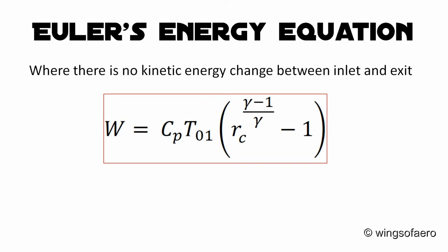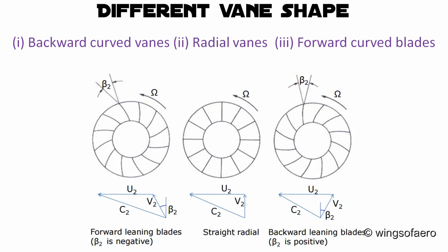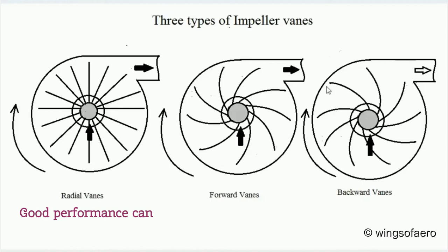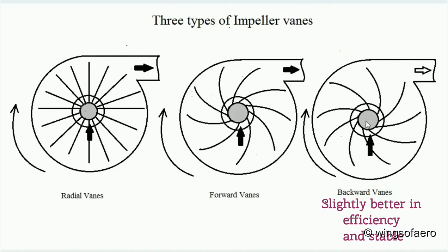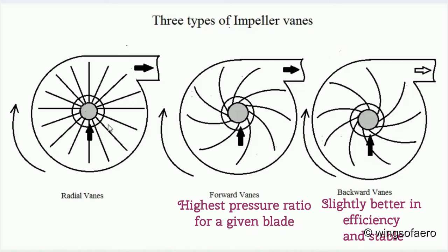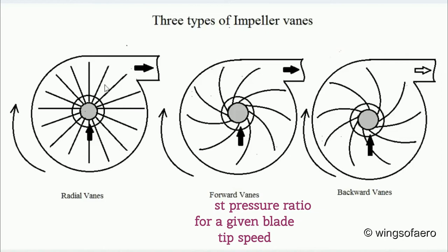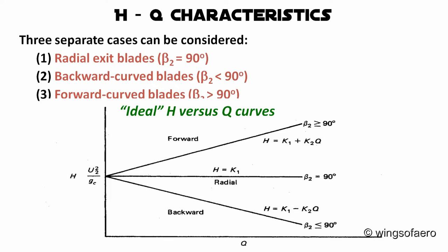Centrifugal effects on a curved blade create a bending moment and produce increasing stress, which reduces the maximum speed at which the impeller can run. Good performance can be obtained with a radial impeller blade. Backward curved blades are slightly better in efficiency and are stable over a wide range of flows compared to radial or forward curved blades. Forward curved blades can produce the highest pressure ratio for a given tip speed, but are inherently less stable, have a narrow operating range, and lower efficiency than backward or radially curved blades.